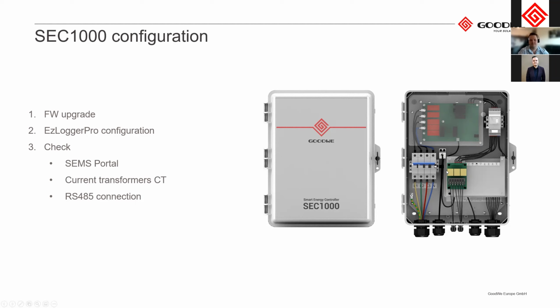It's also very important, so you'll see in the manual which connection point is for which CT, to make sure that the CT matches the phase input on this as well, because this is our voltage reference to our CT reference.